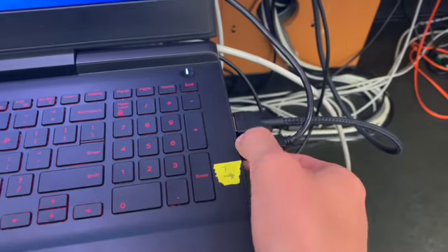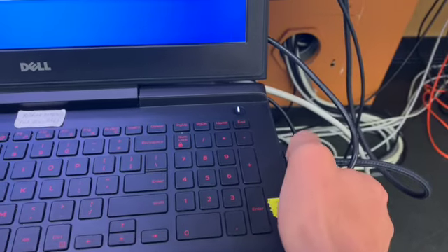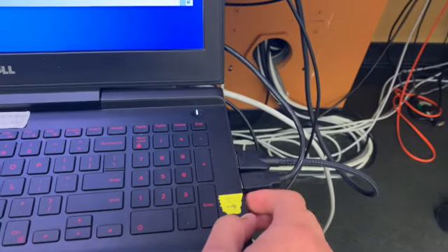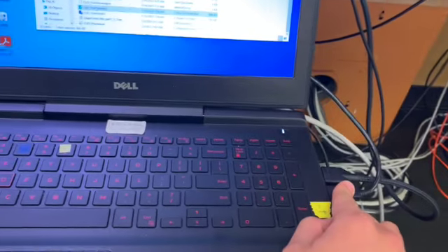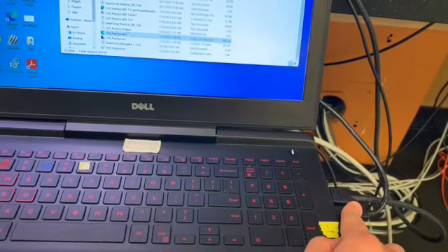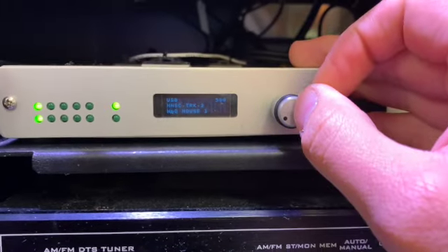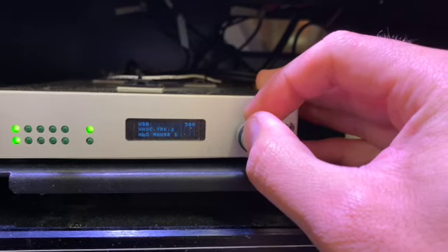But first, we want to make sure we have a few things attached. The first one is a USB cable attached to the FORP response box. This is an HDMI cable attached to the monitor so the patient can view the task while inside the MRI scanner. The FORP response box is responsible for communicating between the task, the computer, as well as the MRI scanner. So once we have that all connected, we're just going to move to the FORP response box and set up the correct control box, button response box.